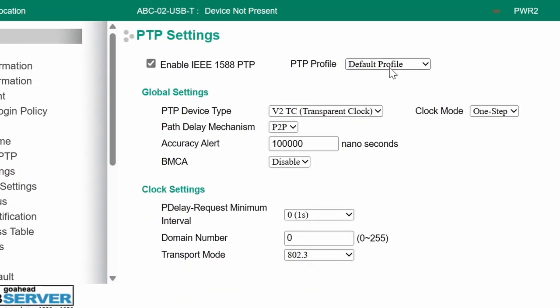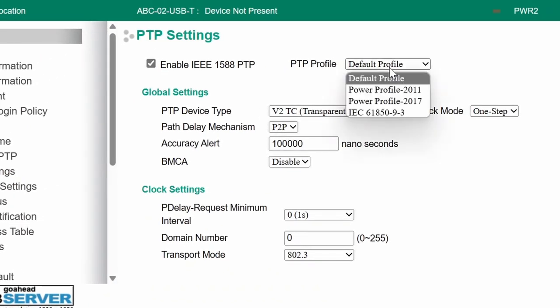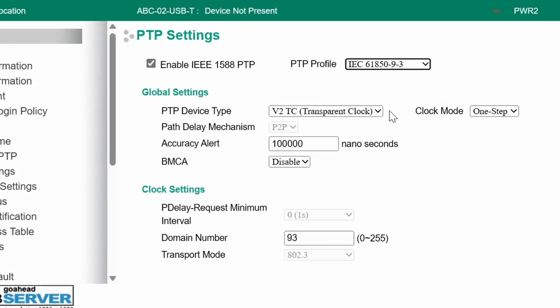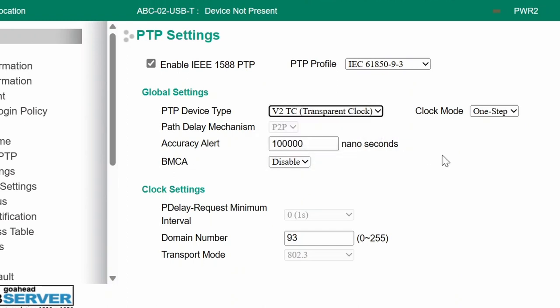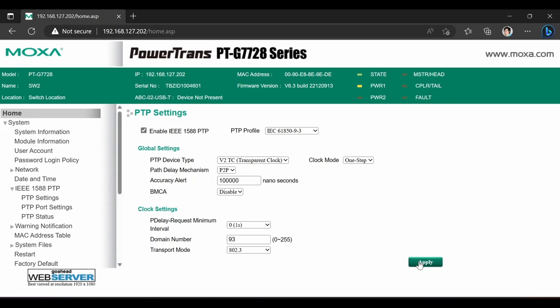I'll enable PTP, select IEC 61850-9-3 profile, ensure that transparent clock mode is used, peer-to-peer mechanism is already locked by the profile, domain is the same as on the rest of the devices, and Ethernet as transport protocol is also automatically set.